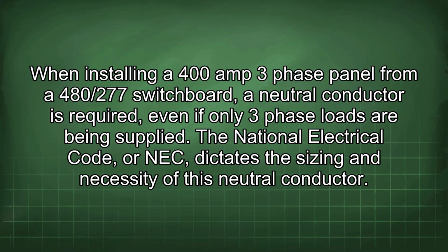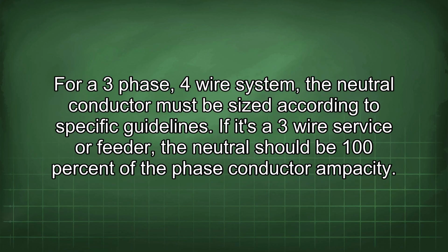When installing a 400 amp 3-phase panel from a 480/277 switchboard, a neutral conductor is required, even if only 3-phase loads are being supplied. The National Electrical Code, or NEC, dictates the sizing and necessity of this neutral conductor. For a 3-phase, 4-wire system, the neutral conductor must be sized according to specific guidelines.